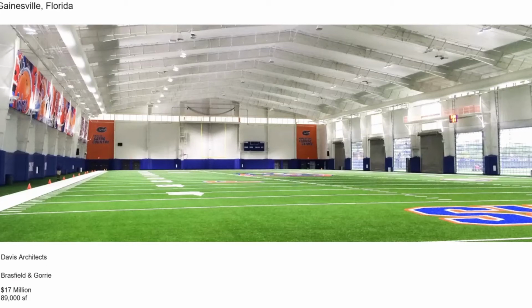When I say commissioning lighting, most of the time you're flipping switches on and off, which is kind of fun, brainless work. But in this situation, there was a huge panel of light switches, and you have to make sure that when you increase it gradually, the lights increase gradually too, that if there's a timer it turns off at the appropriate time, and that the right light switch is associated with the right light fixture. It was probably a half-day event just to make sure all those lights were properly associated with that lighting panel.